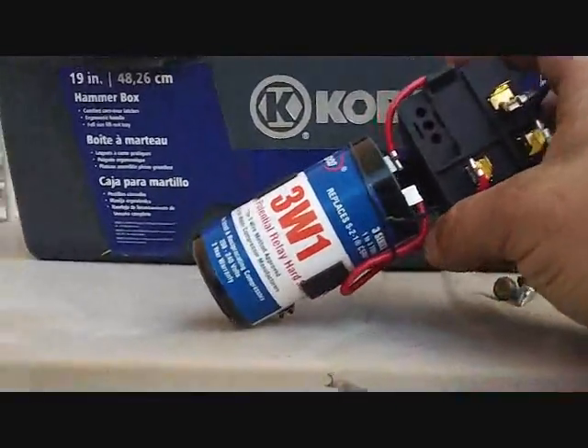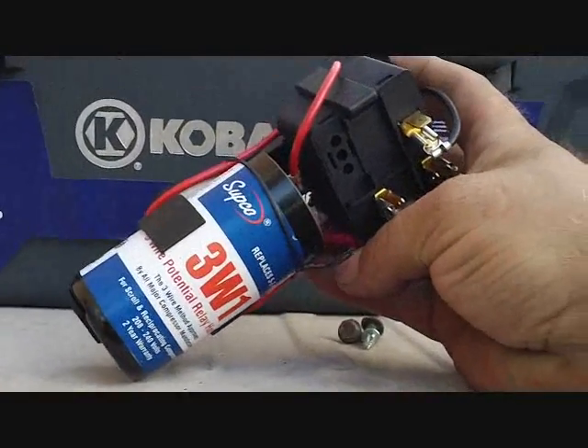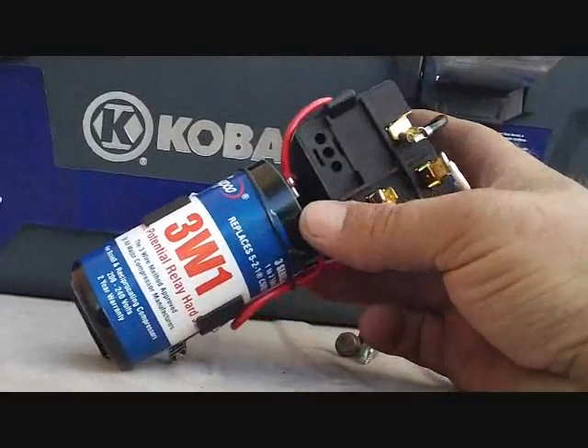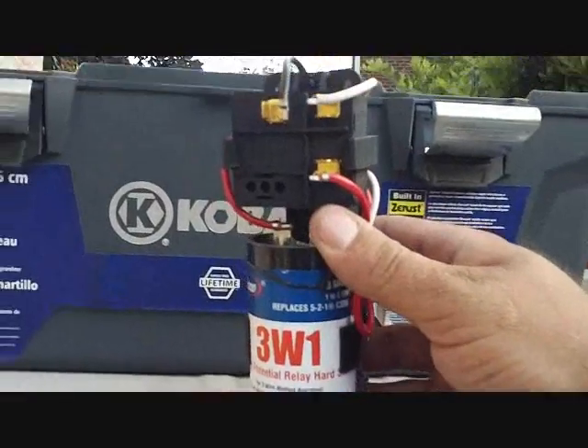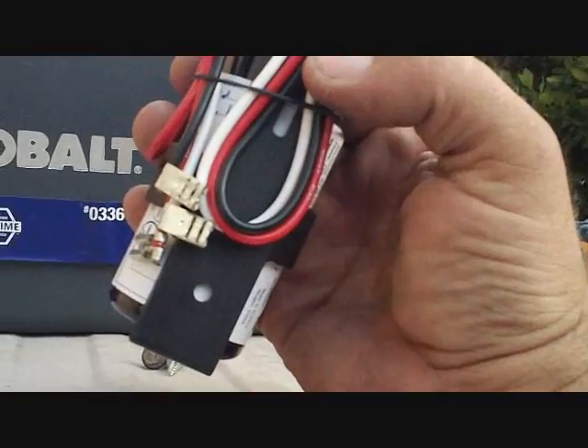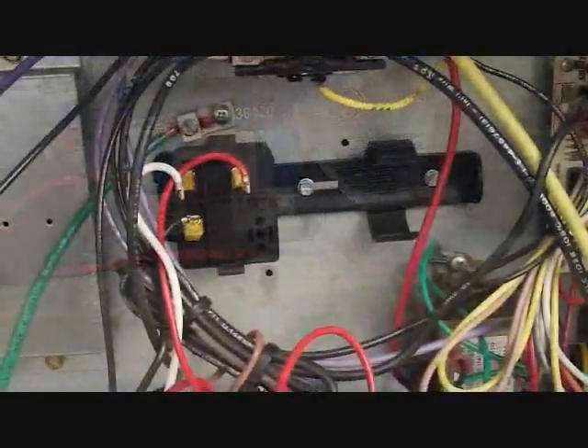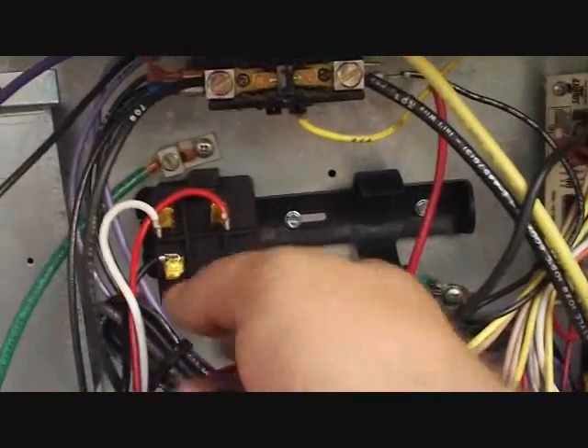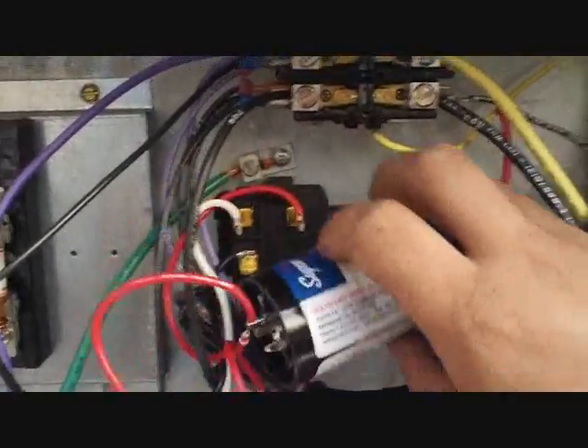So we're going to add a hard start to it. The dual run capacitor is fine, so that wasn't an issue. We only use three-wire hard starts because those are the only ones that really work. This is a Supco version — it says it replaces the compressor saver 521. At Johnstone this month these are on sale, so these are the ones we have. It actually comes with a little mounting bracket, which I really like.